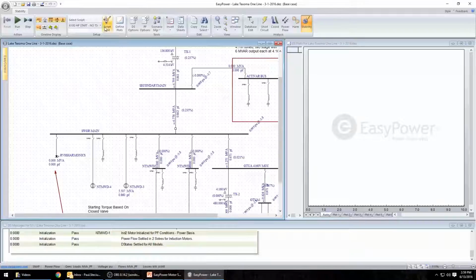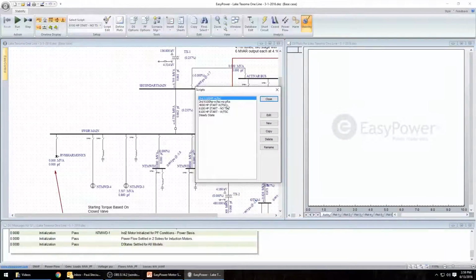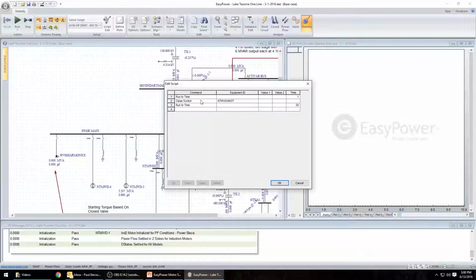It's a 6,100 horsepower start, no TSC in this situation, TSC being a thyristor switched capacitor bank. So in other words, we're going to start this 6,100 horsepower motor here with this one already operating. So if I were to go in here and just do a script edit, I want to show you what we have here. It's a 6,100 horsepower start, no TSC. We do an edit on this, and all we're basically doing here is we're saying run to time 1 second, and close the switch to the motor. This is the switch for this motor right here, this location for that switch, for that motor, and then we run to time 20 seconds. Nothing else is being done in that script other than the closing of the motor switch or motor starter.